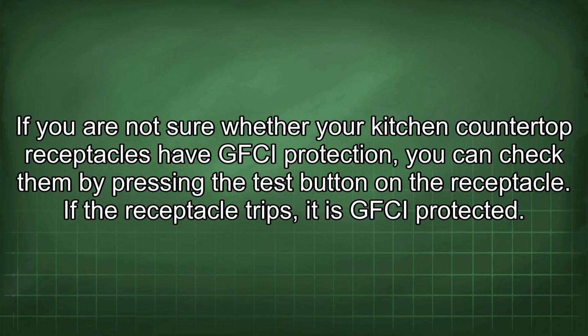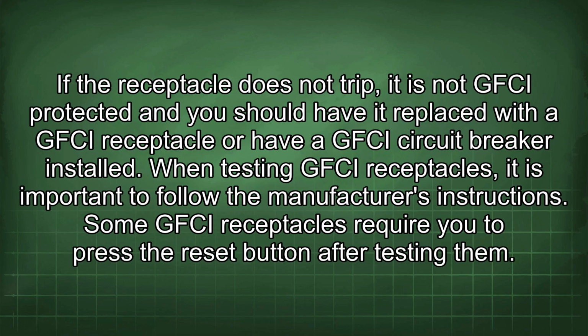If you are not sure whether your kitchen countertop receptacles have GFCI protection, you can check them by pressing the test button on the receptacle. If the receptacle trips, it is GFCI protected. If the receptacle does not trip, it is not GFCI protected and you should have it replaced with a GFCI receptacle or have a GFCI circuit breaker installed.